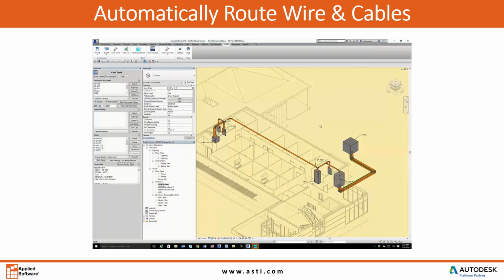And if you look closely, I do have one piece of conduit that's coming off that transformer off the backside of my building that's still green, that it's not orange. And that's simply because I drew that one in there, but I drew an extra piece of conduit. I drew a spare piece of conduit in there that's not being used. And so you can see that there is an empty conduit in there that's not being used. But again, this is putting the intelligence in the conduit.